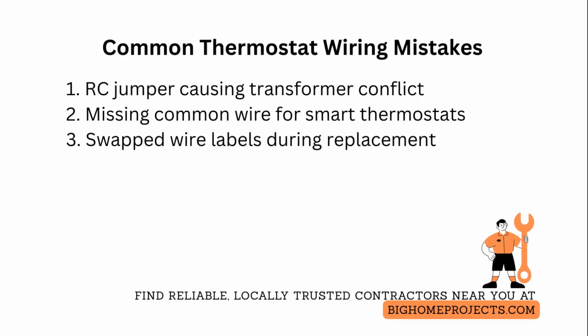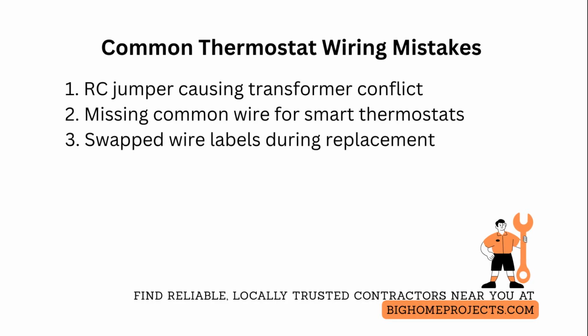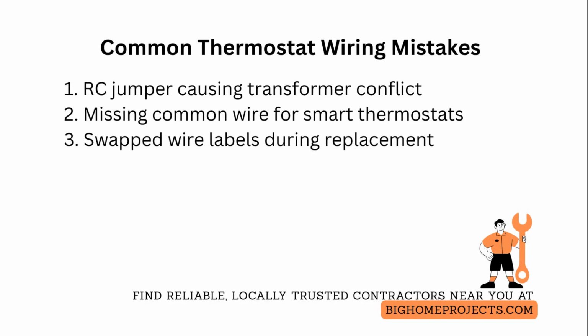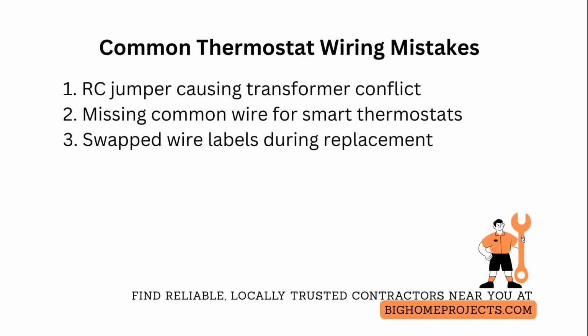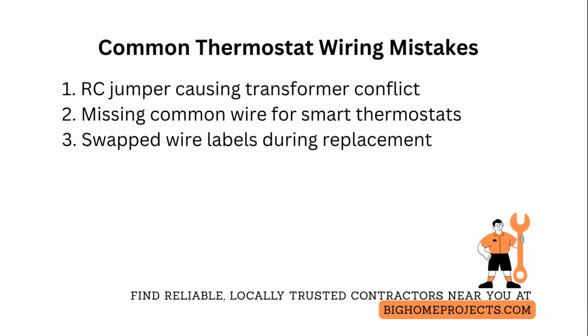The third frequent error is swapping wire labels during replacement, especially with multiple systems wired into a single stat. Fix this by marking each wire at the old thermostat, photographing the connections, and verifying at the equipment control boards to ensure each wire goes to its correct terminal.